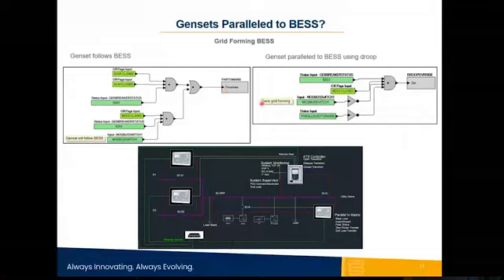If we want the gens to be grid forming instead, then we put a NOT gate behind this Modbus switch. Parallel to mains is not going to be set. And now we're paralleling the gens to the batteries in droop override, droop mode pretty much. And the reason why this would be done is because typically in a grid forming setup where you have multiple resources that are grid forming, like generators and batteries, then droop is the de facto standard for achieving that, at least with today's technology.